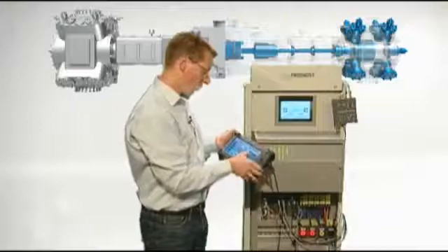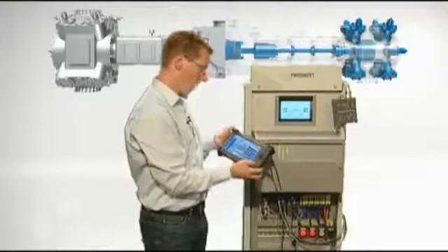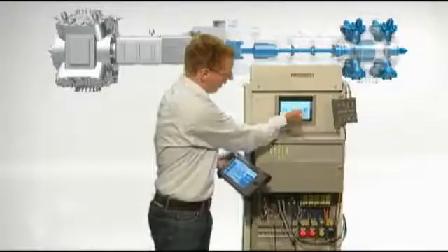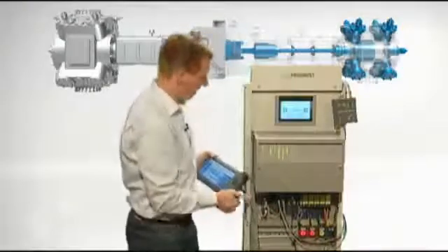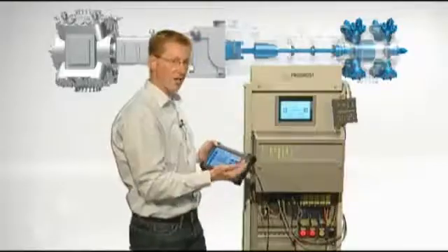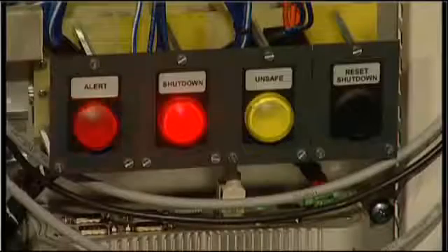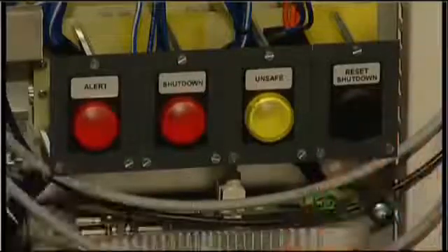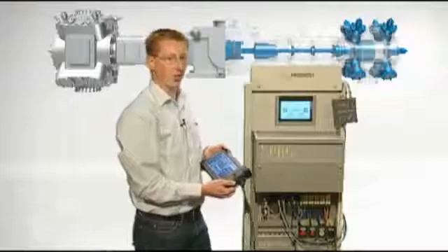Let's switch back to a moderate value, say back to 50 meter per square second. The value has dropped down again. It will now only take a second for the protection rack to recognize machine number 1 is in good condition again. We can now reset the demo rack and are back in good operating condition.